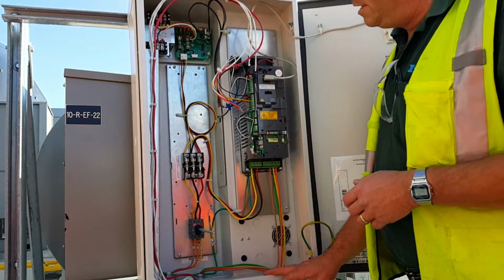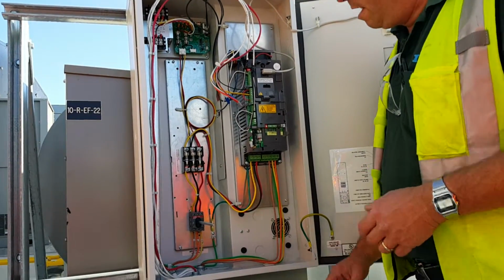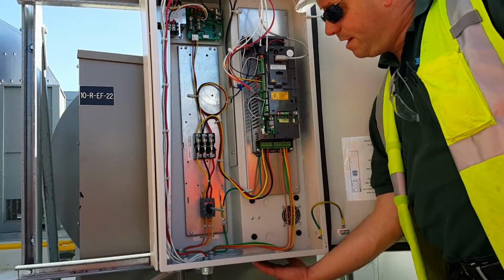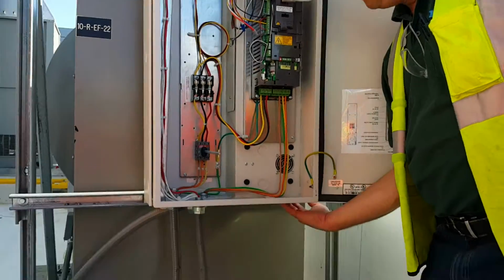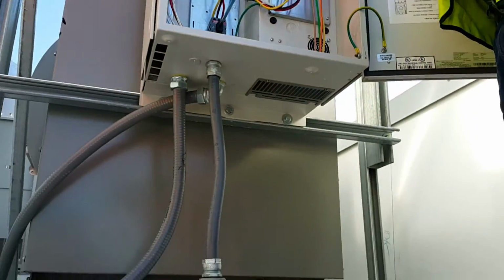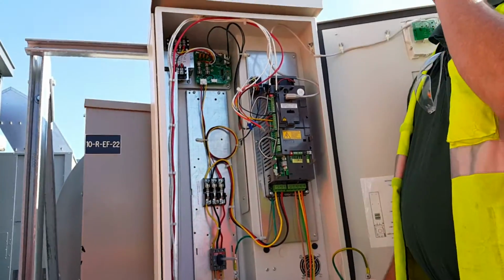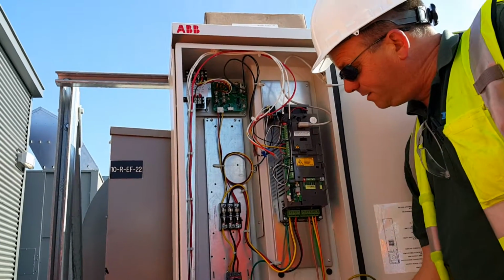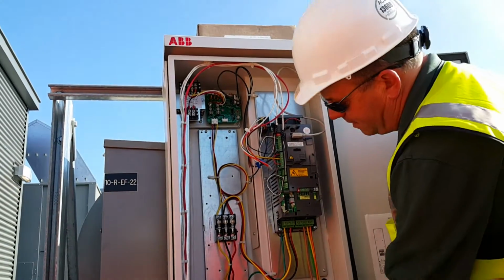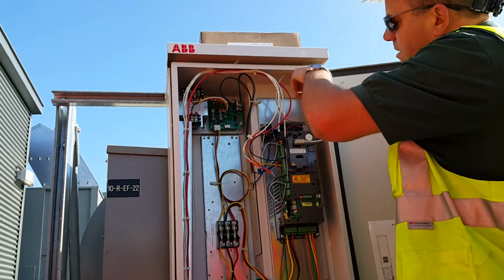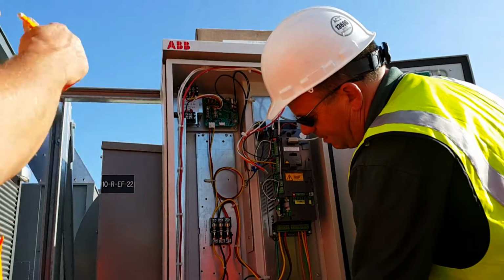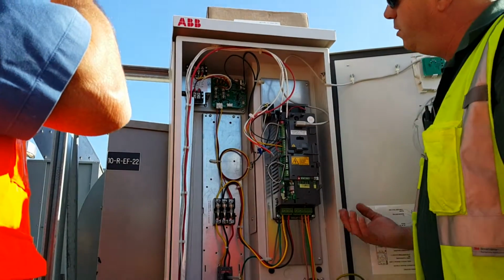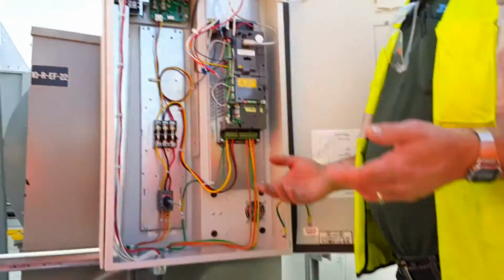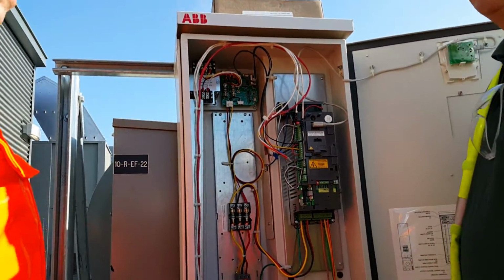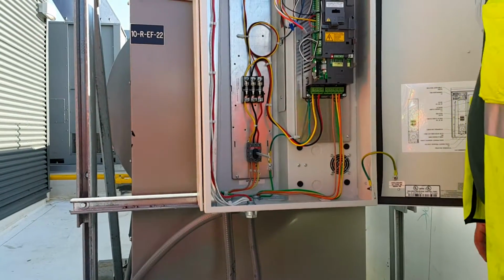On these units, because they're outside, it's even more important. I would recommend putting a filter, dropping this down, putting filter material across here, especially being in the city because you've got a lot of salt going in. And that cooling fan sucks up from up here. The cooling fan is actually behind here on top. And what it does, it blows air up across the heat sink. And that air, if it's salty, as it can be here, is going to get to the fan and that kind of stuff after a while.